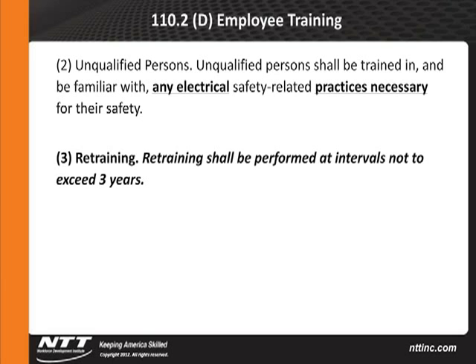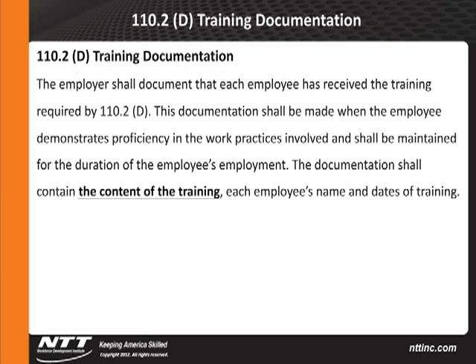Retraining is a new part. Retraining shall be performed at intervals not to exceed 3 years. I think that's going to have a major impact on many of you sitting out there. Training documentation. The employer shall document that each employee has received the training required by 110.2, Section D. This documentation shall be made when the employee demonstrates proficiency in the work practices involved and should be maintained for the duration of the employee's employment.